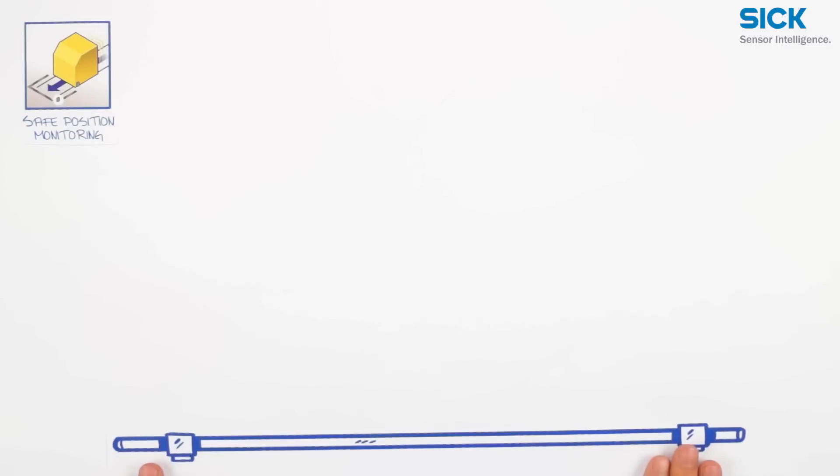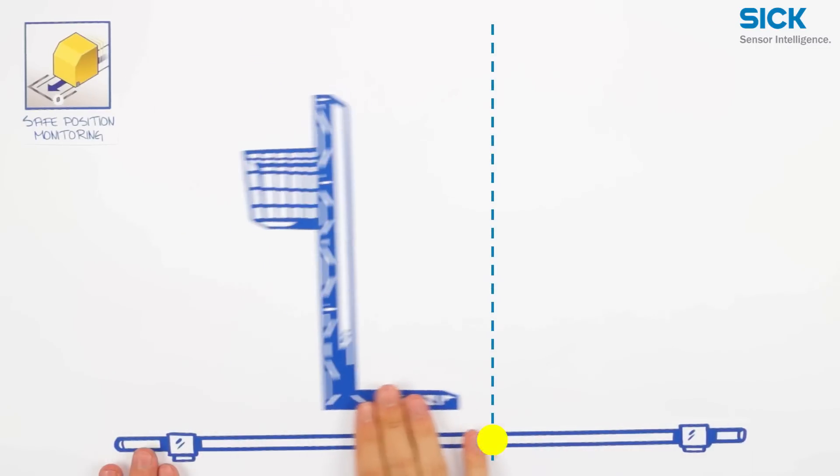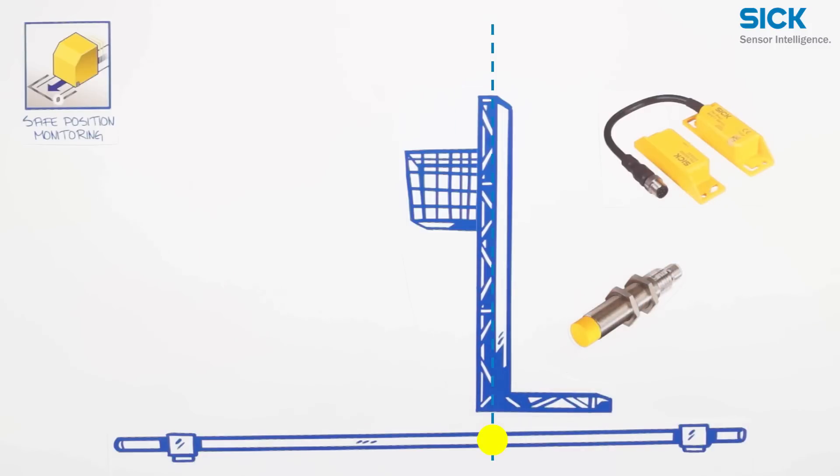Now let's cover safe position monitoring. Some production processes only allow actions to be performed when the machine part is in a certain position. For these applications, you can use non-contact inductive safety switches that are activated by metal or transponder safety switches, which are activated with a coded actuator. To stop the machine safely in the end positions, electromechanical safety position switches can be used.